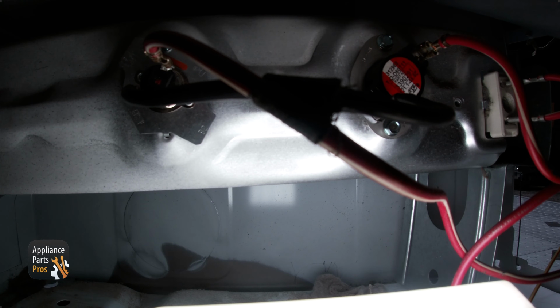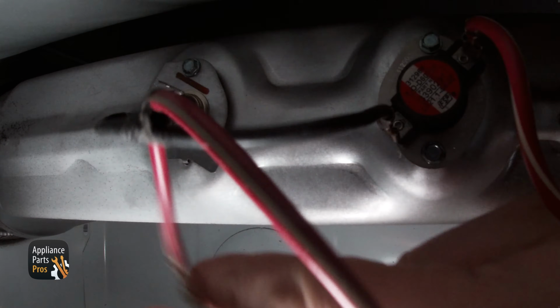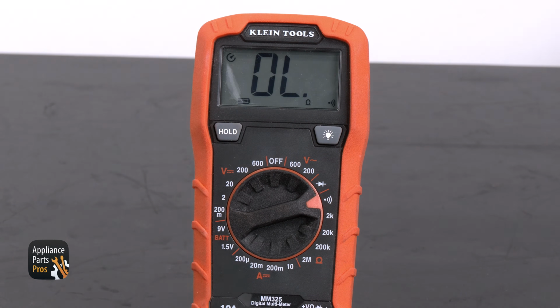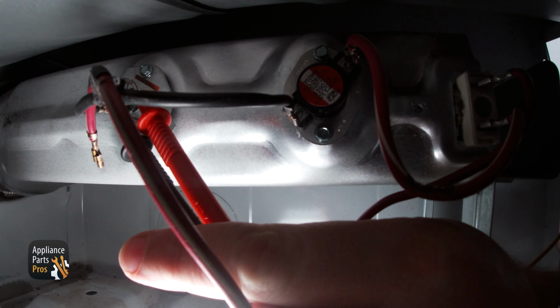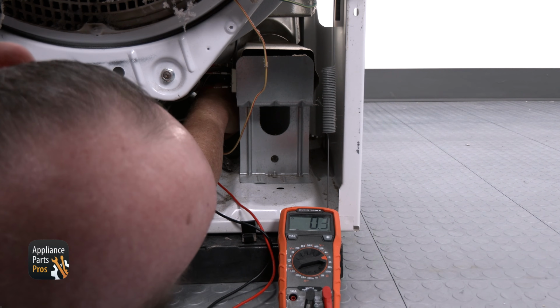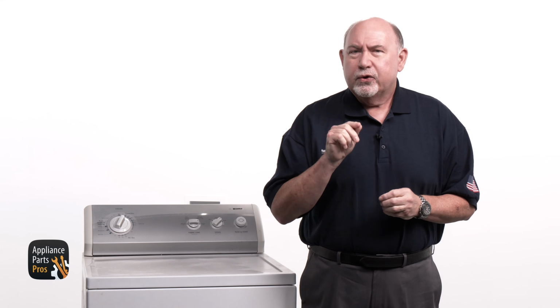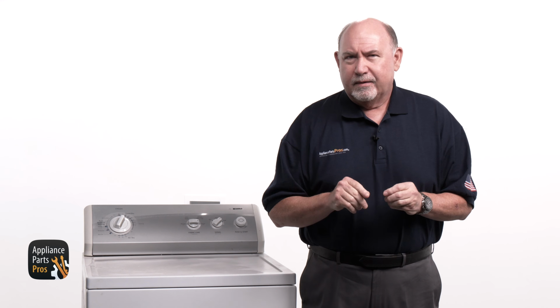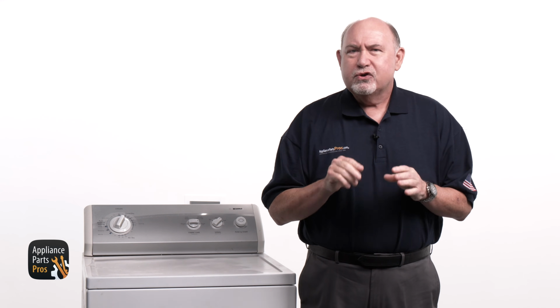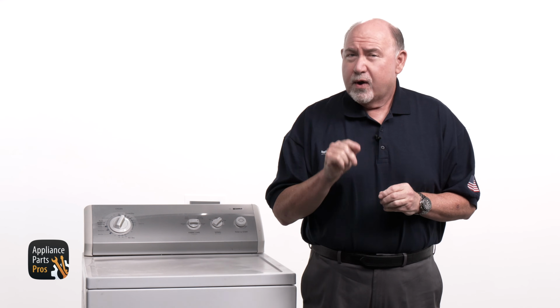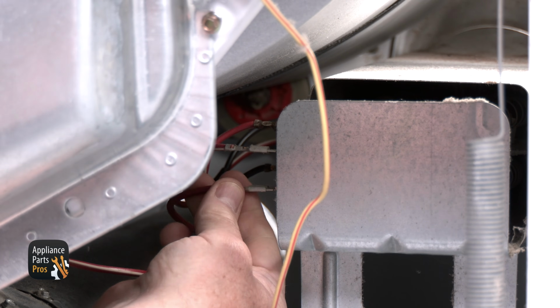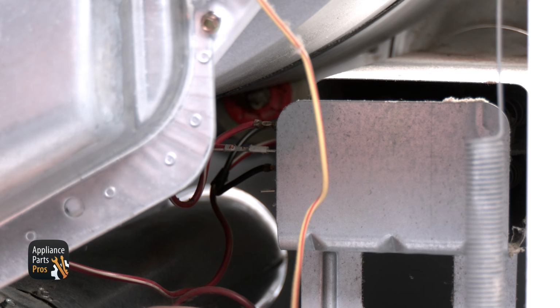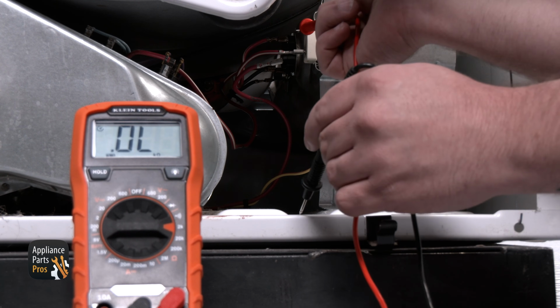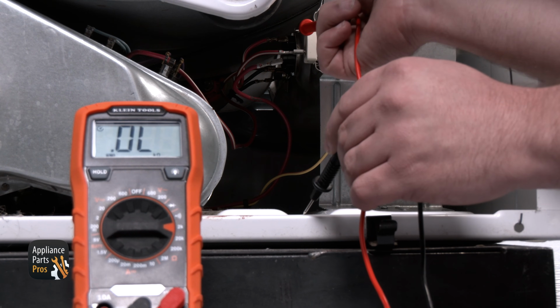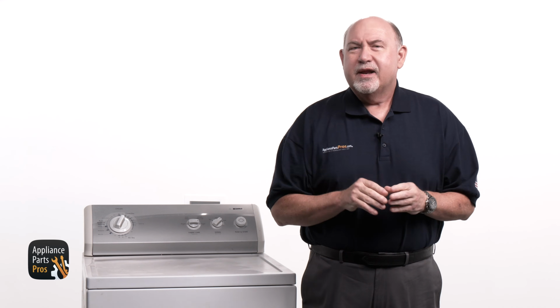Now you can check the high limit cutoff, which is behind the front thermostat. Pull one wire off the cutoff, and with your multimeter set for continuity, use the probes to check across the 2 terminals. If there's no beep from the meter or no continuity, then you'll need to replace the cutoff and thermostat. While you're here, make sure you check the heating element to see if it's grounded. To do that, remove one of the wires from the element terminals and check from one terminal to the metal housing. If there's a beep from the meter or it shows continuity, then the element is grounded and will need to be replaced.